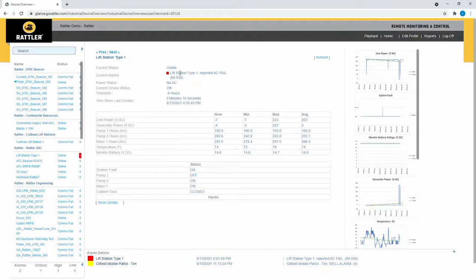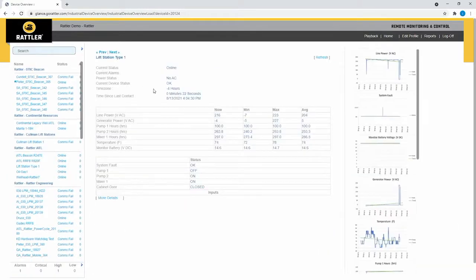So what we'll do is put the power back to being restored. I'll wait for the alarm to come through on my phone here, which it comes through right now. It says that the fault has been cleared, and now you can see on the Glance user interface that the fault is cleared, and you've got line power back to some kind of normal value over here. And that's how simple it is to do remote monitoring and control of lift stations from anywhere.